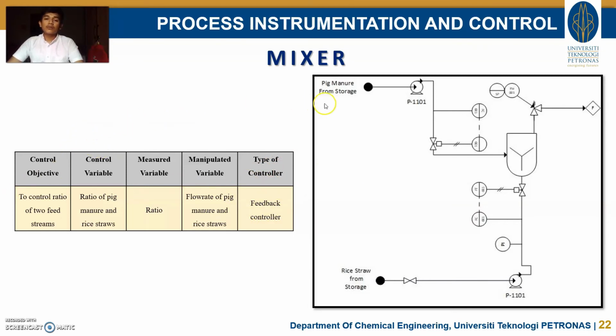For the first equipment, which is the mixer, the control objective is to control the ratio of 2 feed streams, which are the pig manure and also the rice straw stream. The measured variable for this equipment is the ratio. How we manipulate the ratio is we manipulate the flow rate of the pig manure and also the rice straw. So for the mixer, we install a flow controller and flow transmitter for each stream.